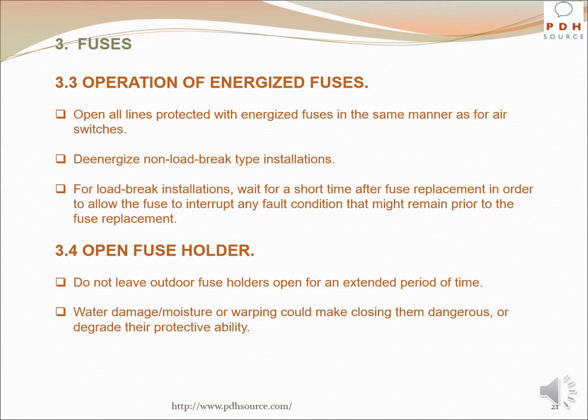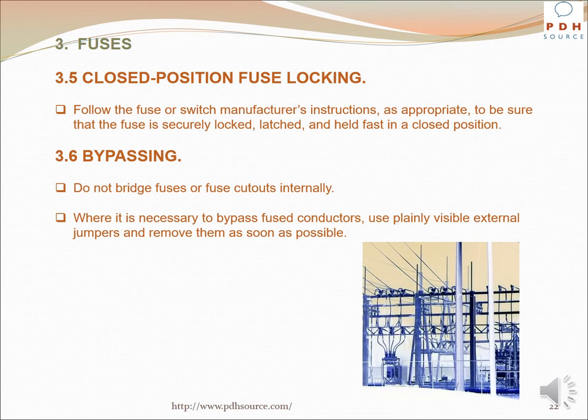For load break installations, wait a short time after fuse replacement to allow the fuse to interrupt any fault condition that might remain. Do not leave outdoor fuse holders open for an extended period of time, as water damage, moisture, or warping could make closing them dangerous or degrade their protective ability. Follow the fuse or switch manufacturer's instructions to ensure the fuse is securely locked, latched, and held fast in a closed position. Do not bridge fuses or fuse cutouts internally. Where it is necessary to bypass fused conductors, use plainly visible external jumpers and remove them as soon as possible.